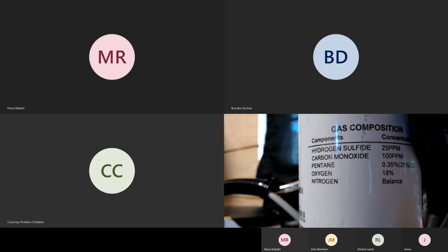Are you guys, you have somebody basically on shift 24/7, correct? Correct. Yep. So for a lot of professional departments such as yourself, what I always recommend is just once a shift, okay, or once a day. So whoever's on first shift in the morning, when they come in and they're doing their check over of the truck and everything else, just have them grab the instrument, throw it on the dock, have it run through and do a bump test, throw it back on there, because technically a bump test is good for 24 hours.